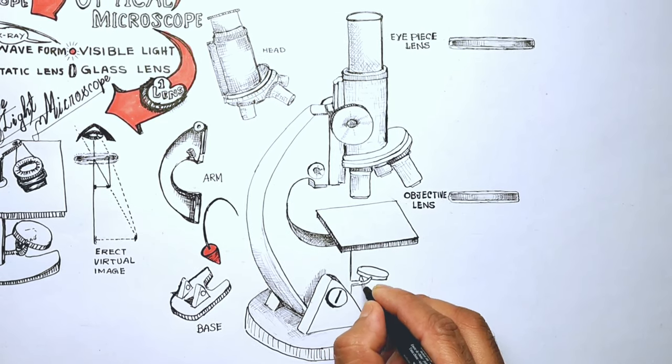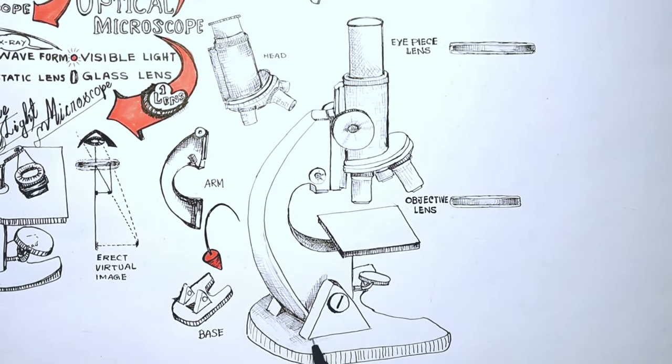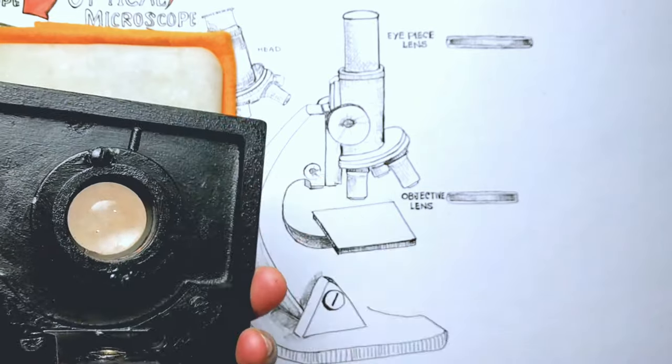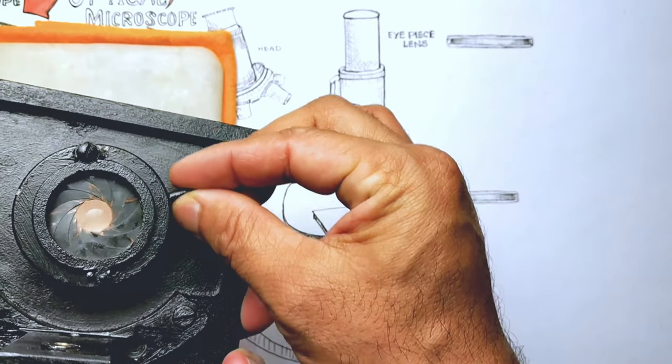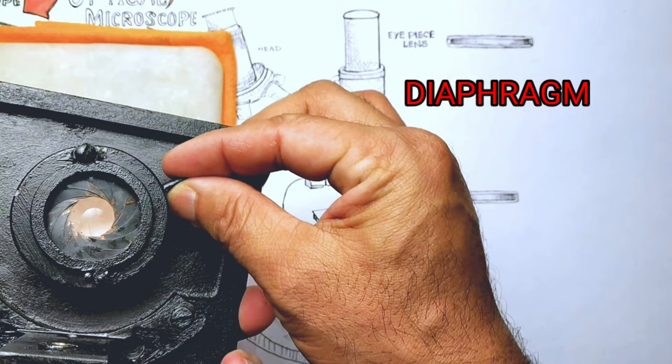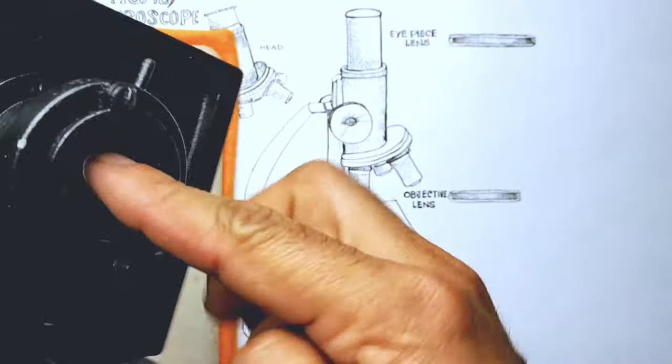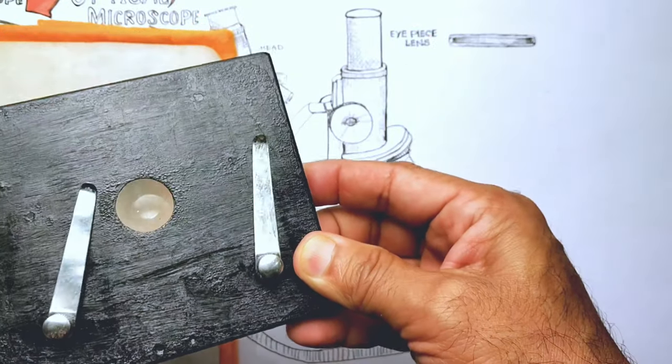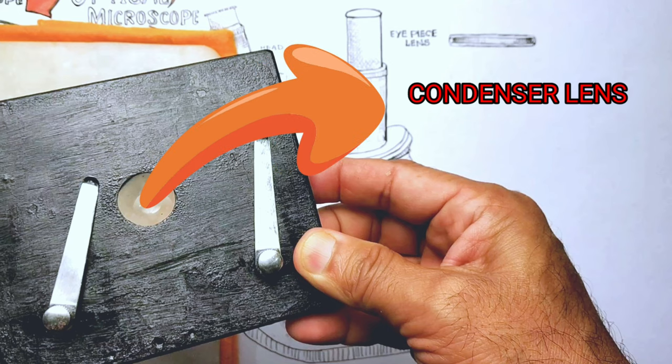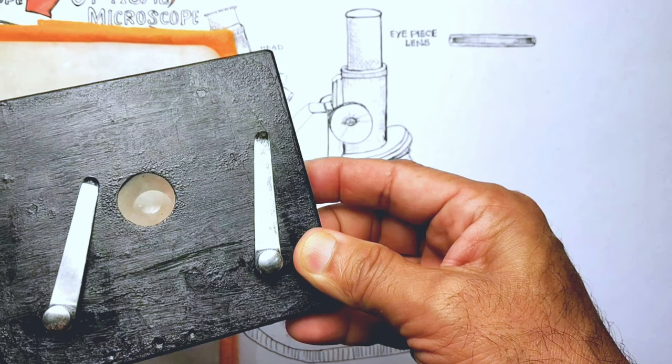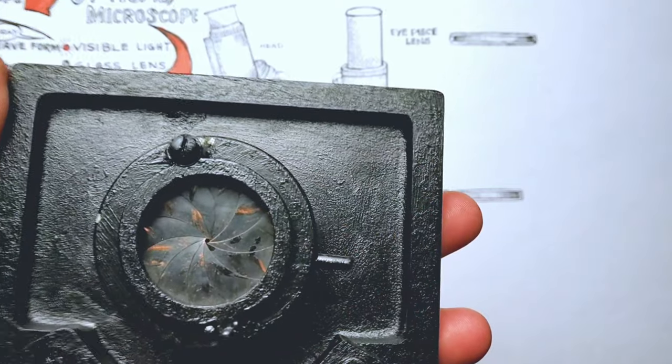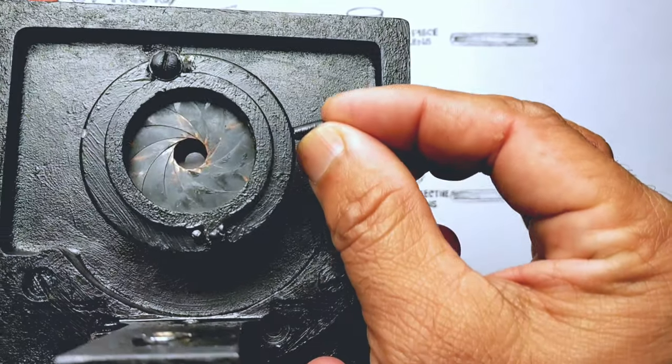The base supports the microscope and houses the illuminator. The illuminator is the light source. It may be a low voltage halogen bulb or a small mirror that reflects the light through the stage aperture. Above the mirror, an iris also known as a diaphragm is also present. The iris helps in controlling the amount of light passing above towards the specimen. There may be a condenser lens just above the diaphragm and immediately under the stage. Light rays from the illuminator are condensed by the condenser lens and focuses a cone-shaped beam of light onto the specimen through the stage aperture.